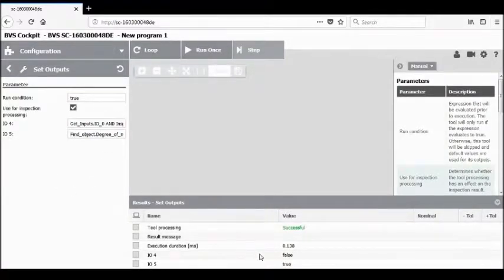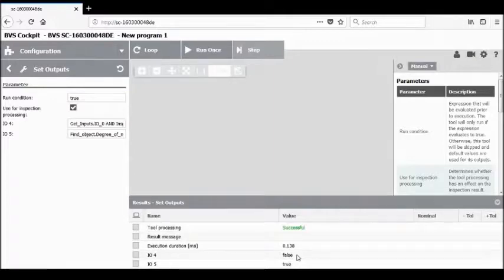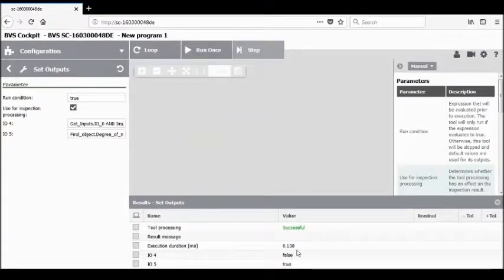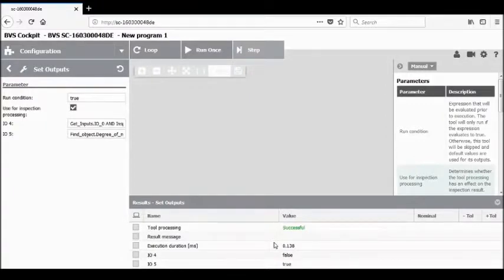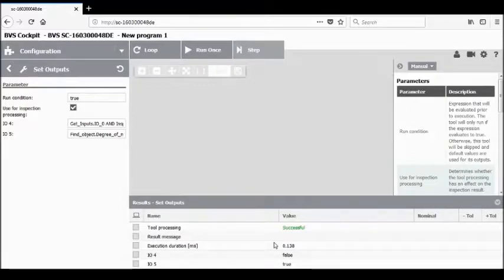You'll notice in the results at the bottom of the screen that IO4 is false, because I do not have an input connected to get inputs 0. Therefore, the output will remain false. We can trigger the combination of get input 0 and inspection processing together, so we can use logic coming in externally from another source. For example, if a process is taking place simultaneously that must be executing for the camera's inspection to be valid, we can combine these two using an AND statement.